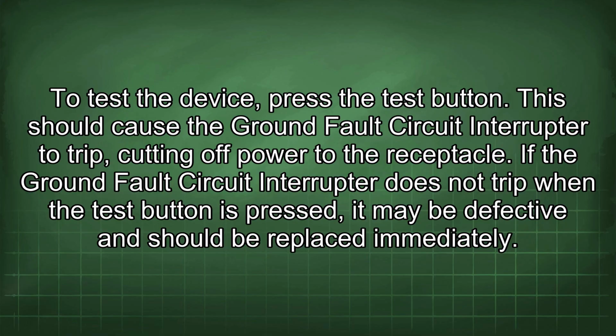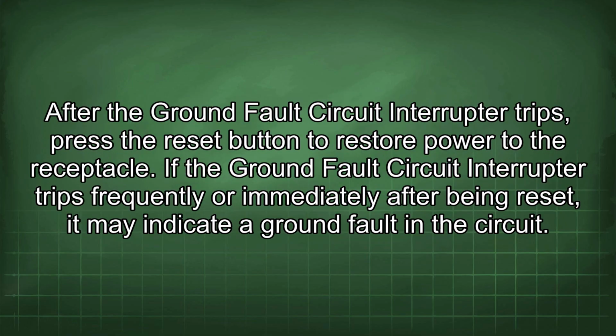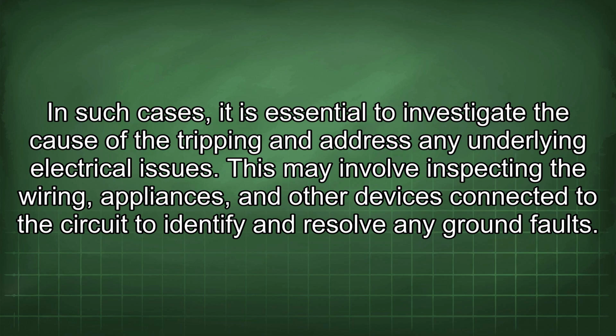If the ground fault circuit interrupter does not trip when the test button is pressed, it may be defective and should be replaced immediately. After the ground fault circuit interrupter trips, press the reset button to restore power to the receptacle. If the ground fault circuit interrupter trips frequently or immediately after being reset, it may indicate a ground fault in the circuit. In such cases, it is essential to investigate the cause of the tripping and address any underlying electrical issues. This may involve inspecting the wiring, appliances, and other devices connected to the circuit to identify and resolve any ground faults.